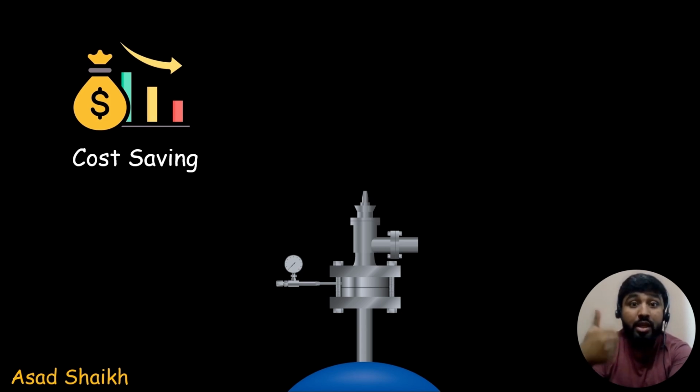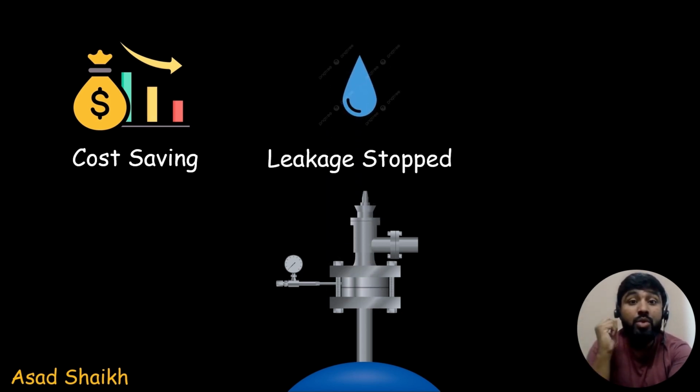The second thing it will help you with is to reduce your leakage rates. How is that possible? Because your rupture disc completely seals it. Even if your relief valve is in closed position, there is still going to be minor leakage going out. So for fugitive emission cases, this is a perfect combination for you to use. Your leakage rate is almost equal to none.